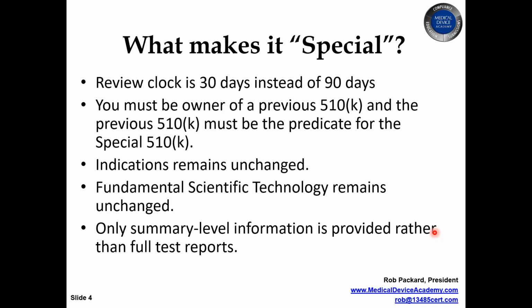So one of the things they're looking for is you summarized the information for your testing. So for instance, we redid this verification test using the same method, the same acceptance criteria, and got the same results. That's the kind of summary they want. You need to be a little bit more specific than that, but a half a page summary explaining what the test method was, what the acceptance criteria was, the number of samples, that's what they're looking for.